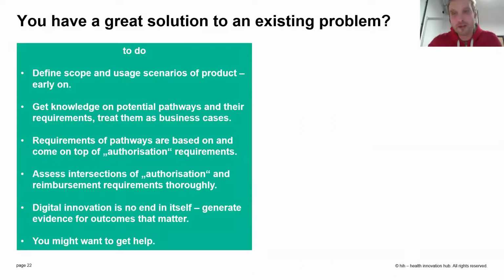So first of all, very important, at the very beginning, early on, when you're developing your product, define the scope and the usage scenarios of this product as specifically as possible. So think about who's your customer. Is it the doctors? Is it hospitals? Is it patients? Is it used in therapy? Is it used in diagnosis? Is it used in rehabilitation or whatever? Get knowledge on these potential pathways that you could enter into the system through, and the specific requirements.